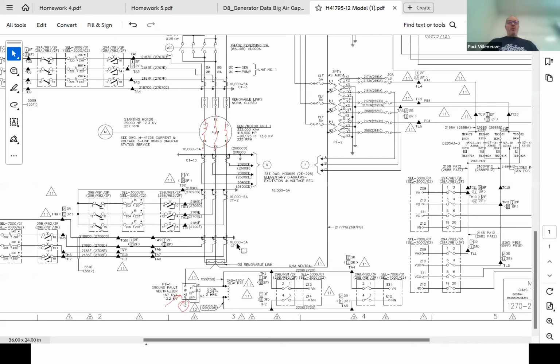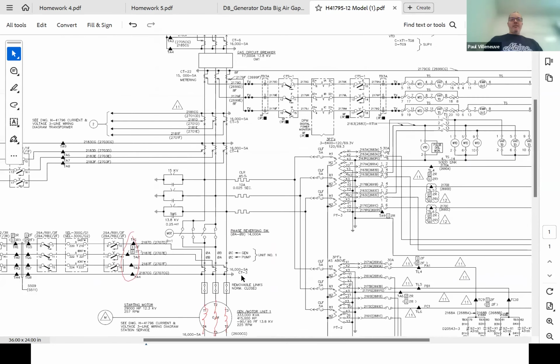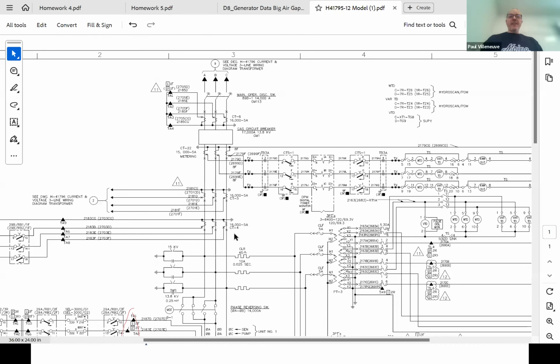Remember what we talked about - the whole purpose of this drawing is, Wyatt needs to run a test. He needs to know, okay, I need to go ahead and grab onto TA1, TA2, TA3, and TA4 on 2187 or 270, whatever, to do some testing. That shows all the terminal connections, but it also shows the terminal connections on the generator. I'm going to really blow your minds if I can find it here.